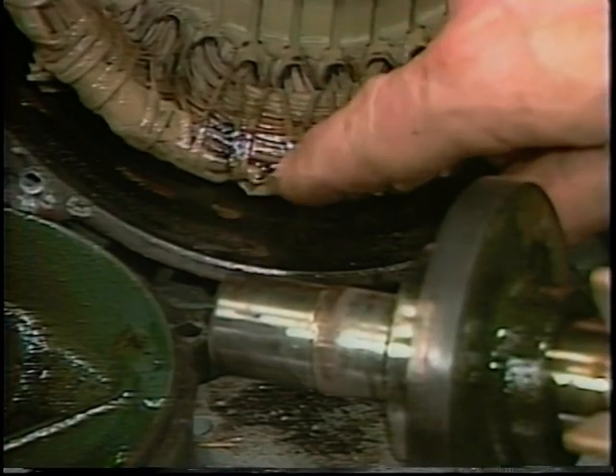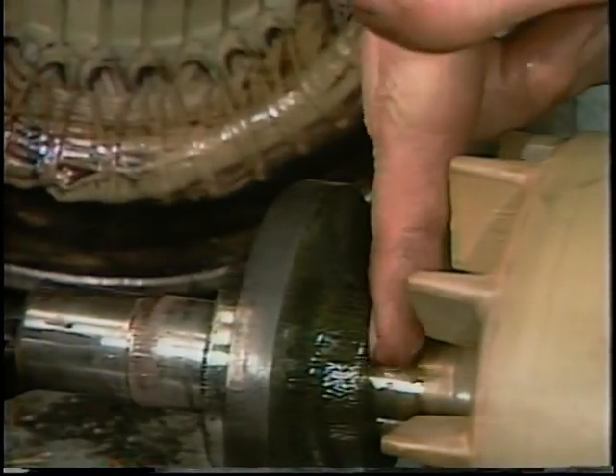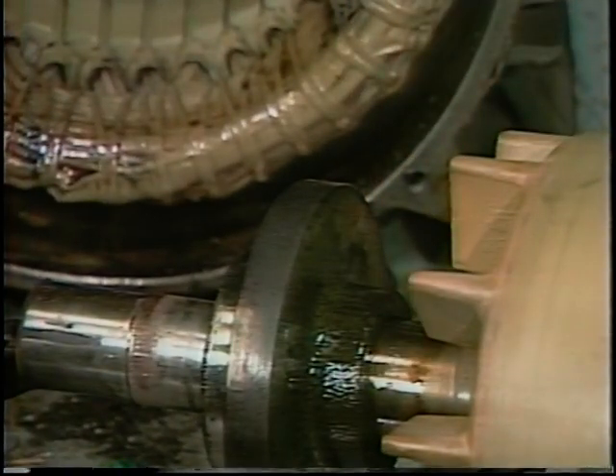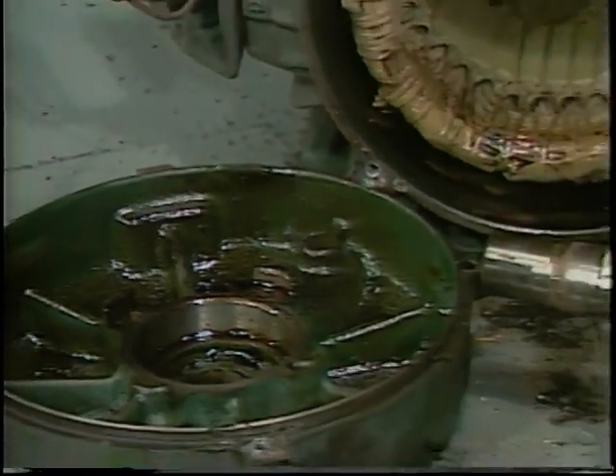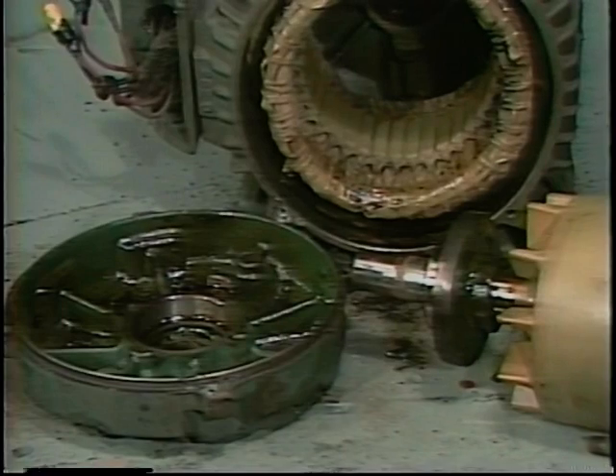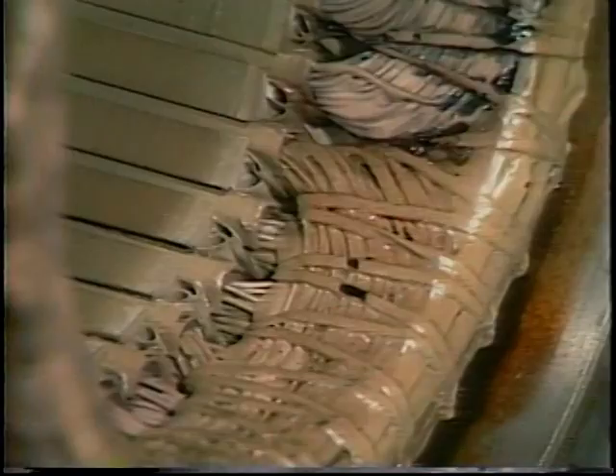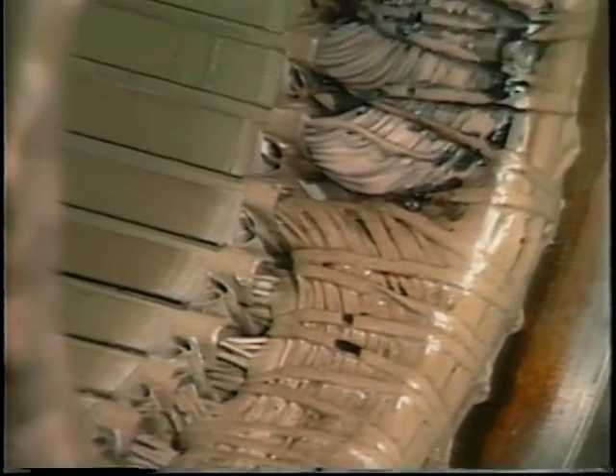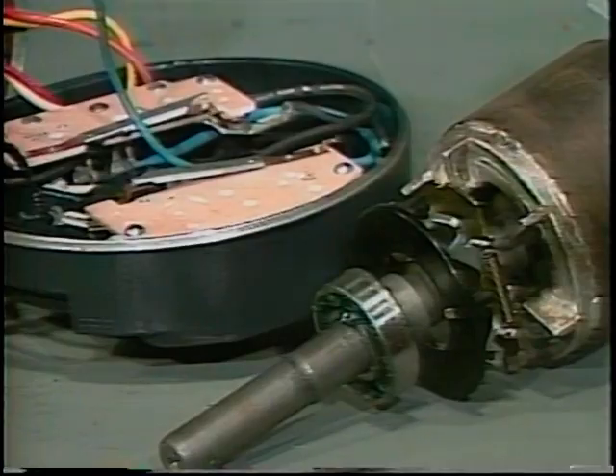Some kinds of insulation material can be damaged by oil, which may have leaked out of the bearings. Check for bad bearing seals. The oil may have been left by oily air pulled through an open motor. In either case, careful cleaning is essential, but do not use solvents, which could also damage insulation materials. Localized burnt areas on the winding insulation or taping probably mean a short of some kind. The winding should be checked further before the motor is put back into service.